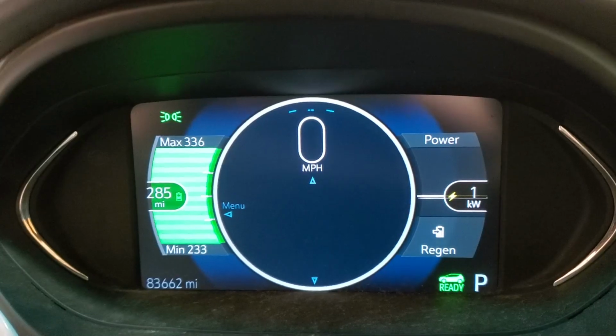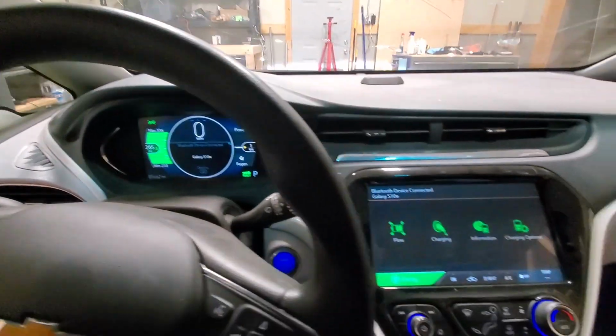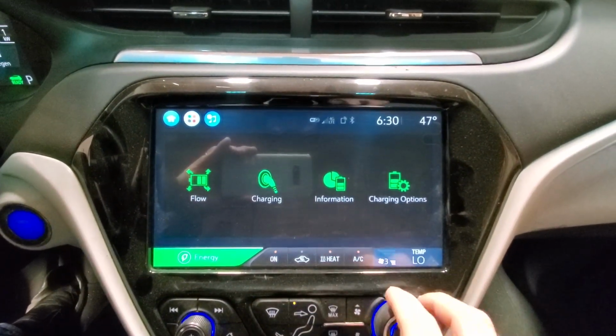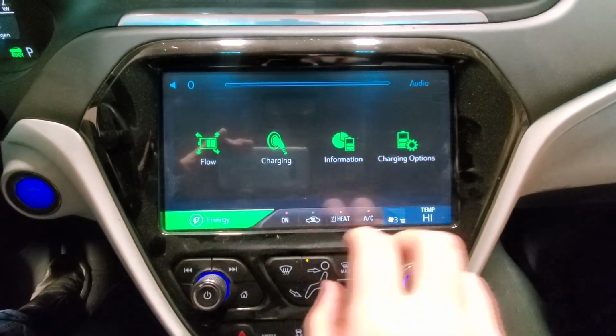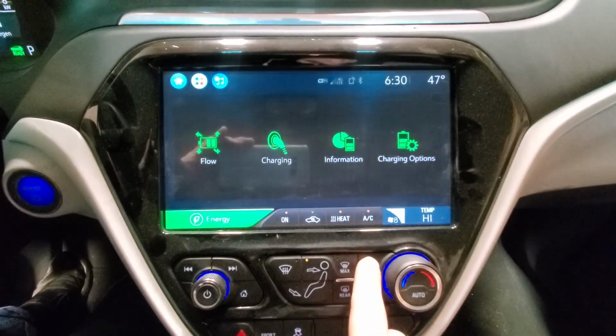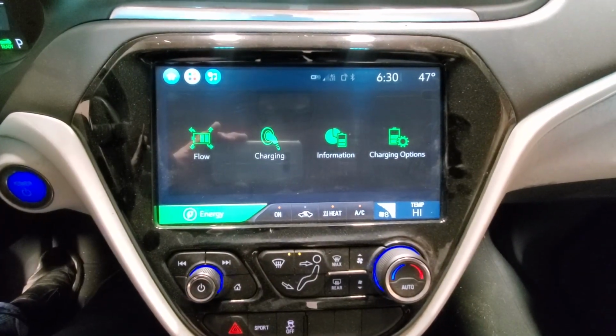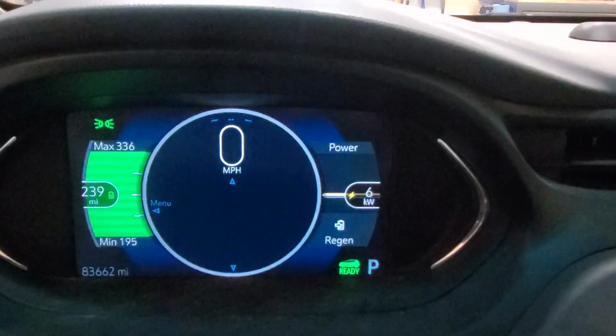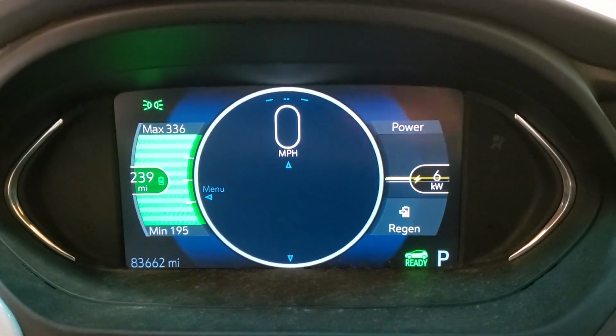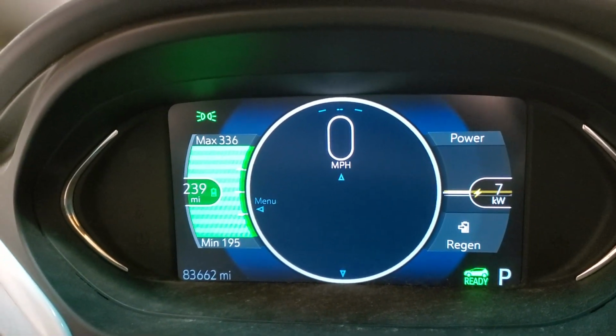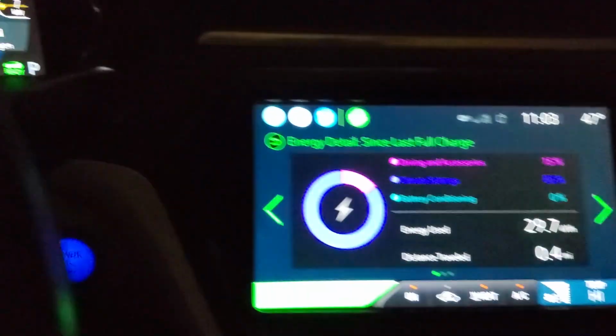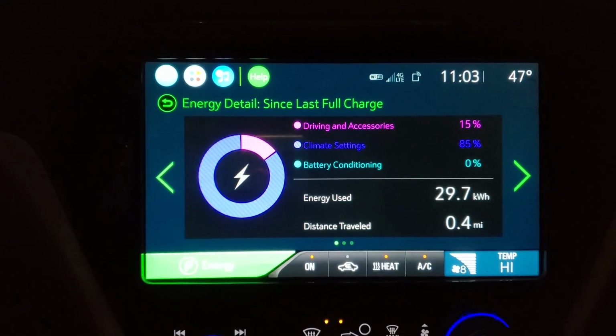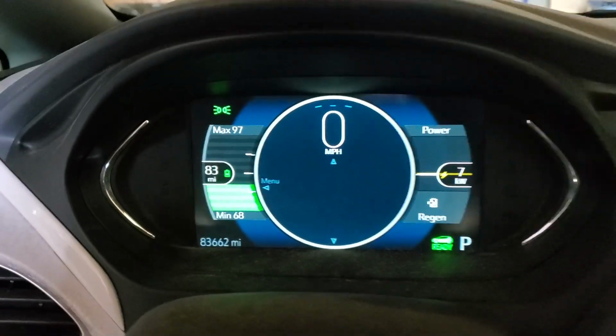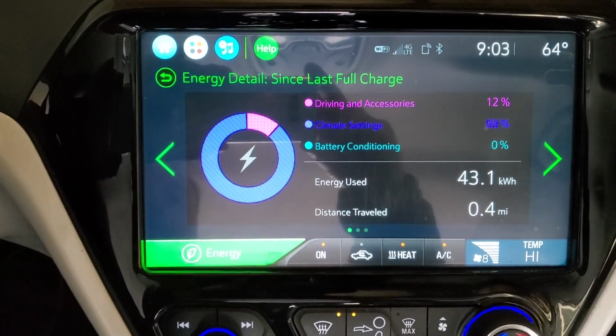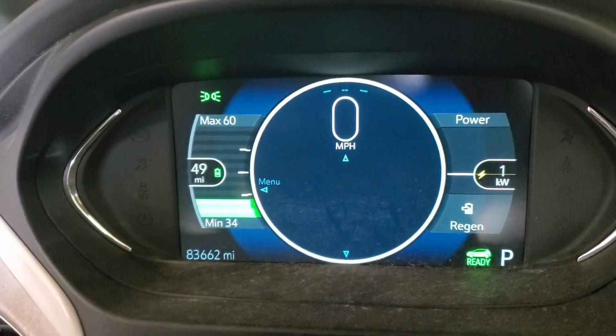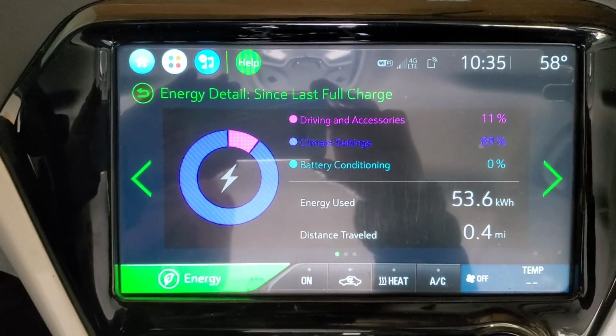Before starting disassembly, I fully charged the battery in the Bolt and got some diagnostic information. Then I turned the heater on in the car to full blast and let it run for a few hours to bring it down to about 20% battery capacity. This is low, but not low enough to potentially degrade the battery if it sits like this for a month or two. I'm doing it partly for safety, since a 335 volt pack is slightly less able to kill me than a 400 volt pack, and because when lithium-ion batteries are charged they expand a little. Since I'll be disassembling the modules, I don't want to put more physical stress on them than necessary.